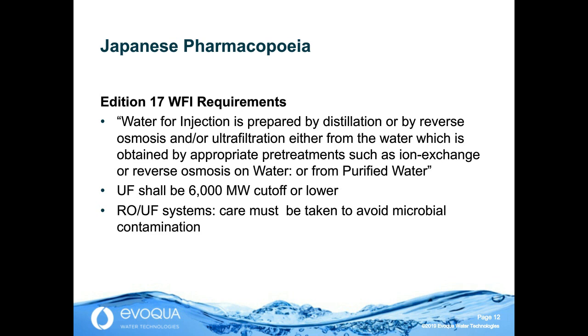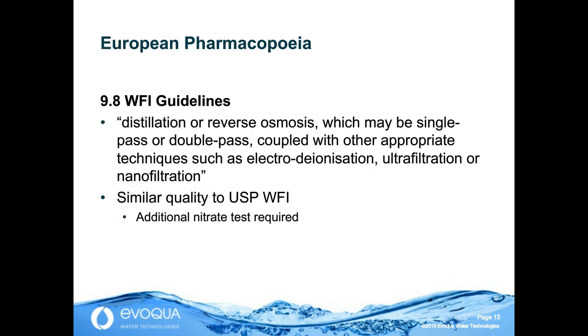If we look now at the new European guidelines, distillation or RO, which may be single pass or double pass, so either 1 or 2 pass RO coupled with appropriate techniques such as electrodeionization, ultrafiltration, or nanofiltration. The water quality of all of these 3 major pharmacopoeial groups is the same for critical quality attributes. So here again, although both membrane processes are mentioned, RO and ultrafiltration, it's not an explicit requirement for both. So we'll look at what's the logic of how to put these systems together.